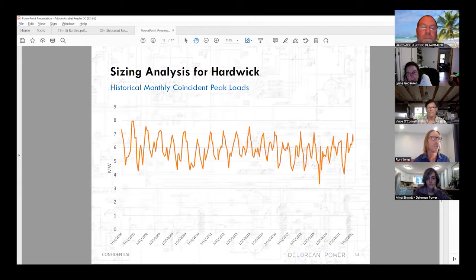Size analysis for Hardwick. So we looked at the monthly load during coincident peaks, going all the way back to 2004. Here you see the megawatts dipping up and down to a peak here in 2005 of about 7.9, 8 megawatts, dipping down in several instances to the kind of 4.5 megawatt mark, and then in one what seems like a slightly anomalous event, dipping down to 3.5 megawatts.